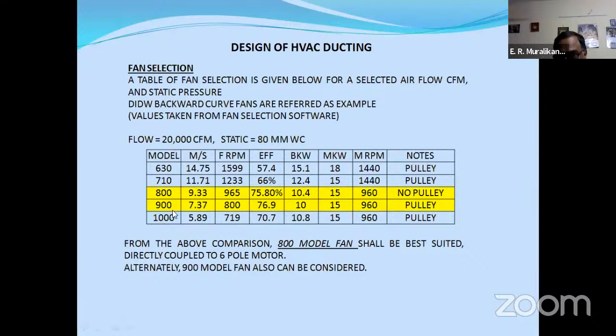Now, each fan will give different velocities: 14.75 meter per second, 11.7, 9.3, 7.3, 5.89. Now, what is the fan RPM? Here is where we actually save on cost and also the running cost, both. How? I will just brief you. Now, in this model, the 800 model, the fan RPM for the selected flow is 965 RPM, which is giving you an efficiency of 75.8%, and BKW 10.4, motor kilowatt is 15, and motor RPM is 960. So we don't need to put any pulley here. It will be direct driven, because a pulley will also have some friction loss, belt loss. So this is the first advantage we are getting.